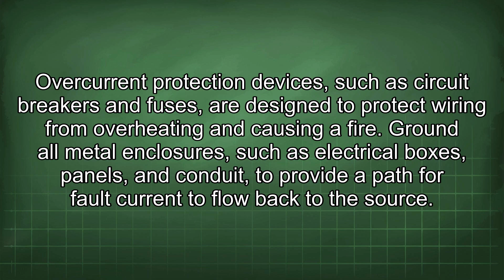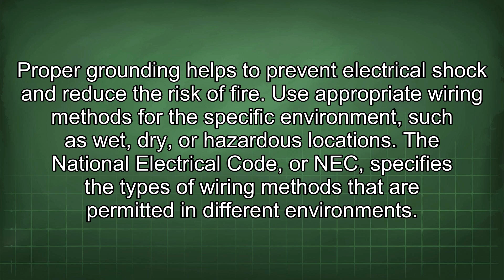Ground all metal enclosures, such as electrical boxes, panels, and conduit, to provide a path for fault current to flow back to the source. Proper grounding helps to prevent electrical shock and reduce the risk of fire. Use appropriate wiring methods for the specific environment, such as wet, dry, or hazardous locations. The National Electrical Code, or NEC, specifies the types of wiring methods that are permitted in different environments. For example, non-metallic sheathed cable, Romex, is permitted in dry locations, while rigid metal conduit is required in wet or hazardous locations.